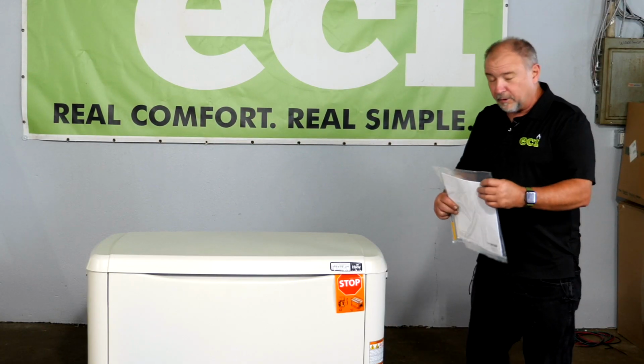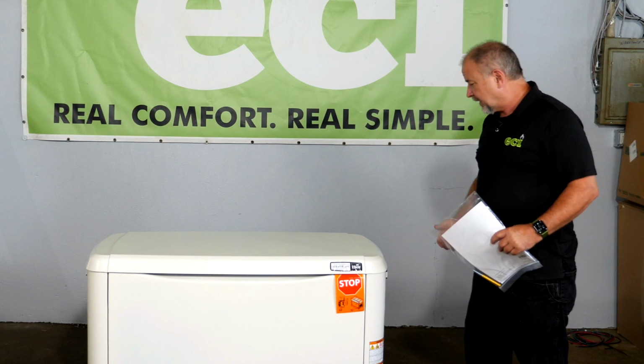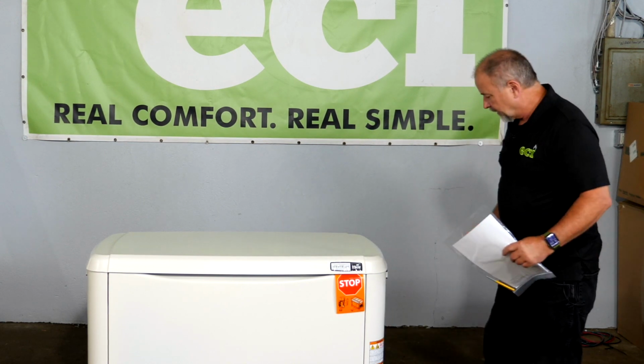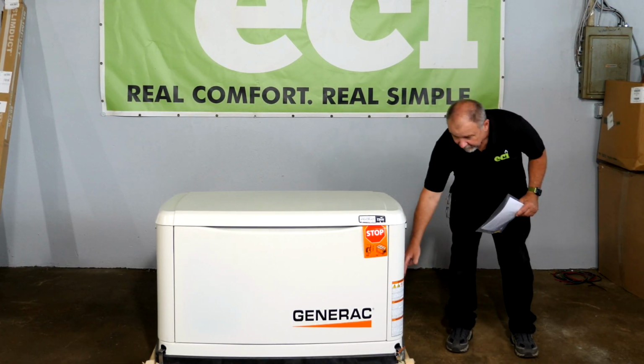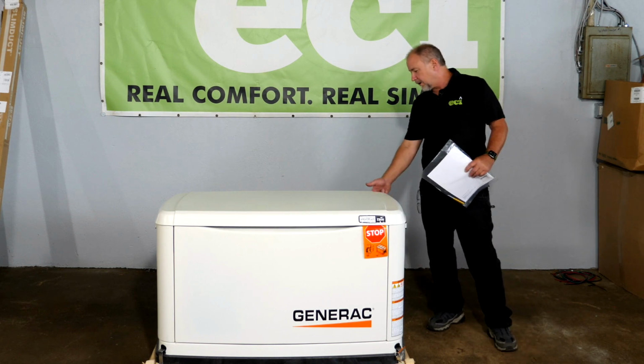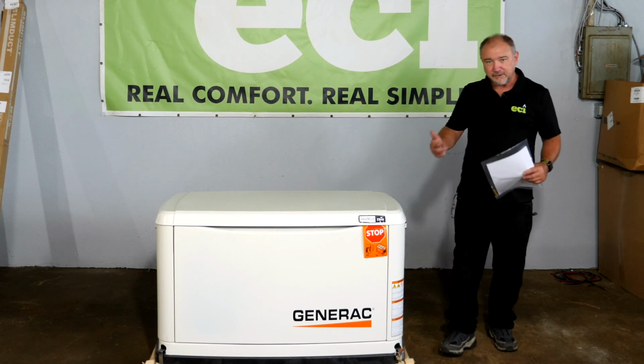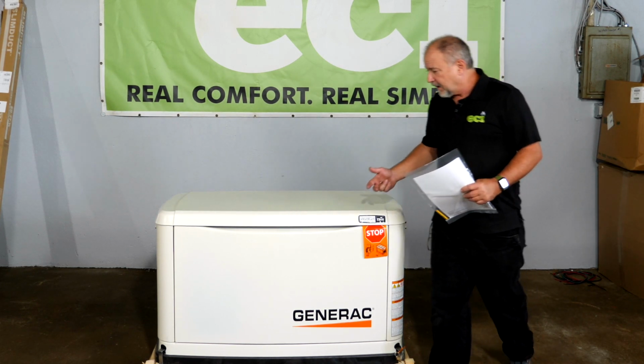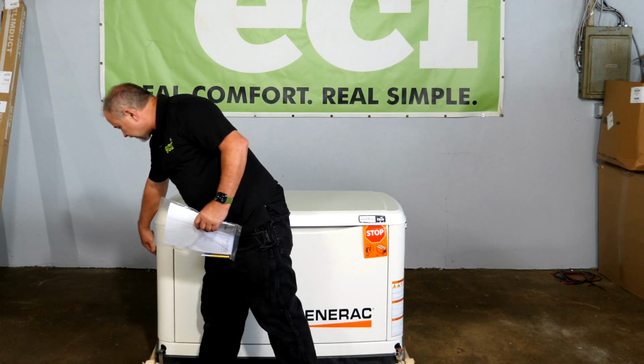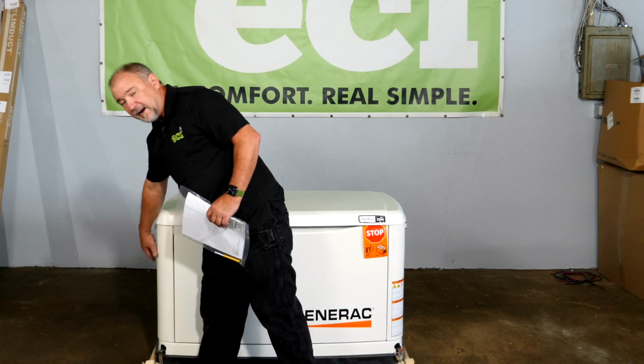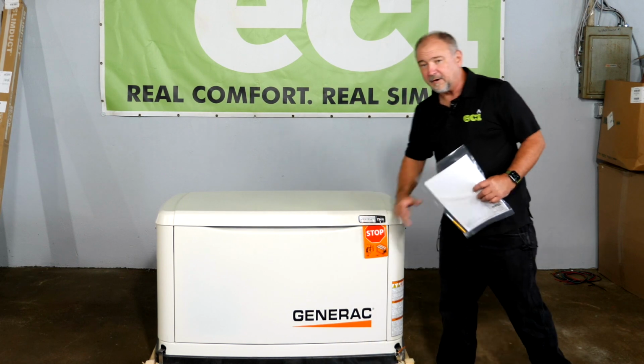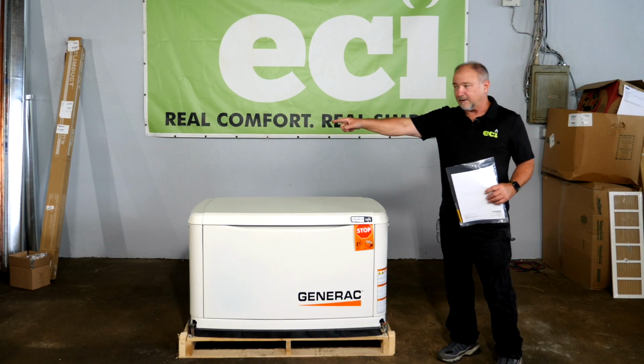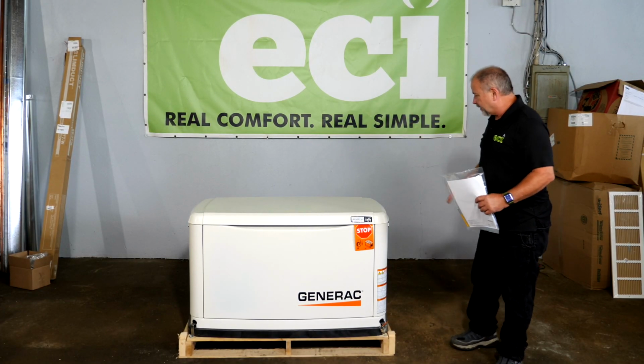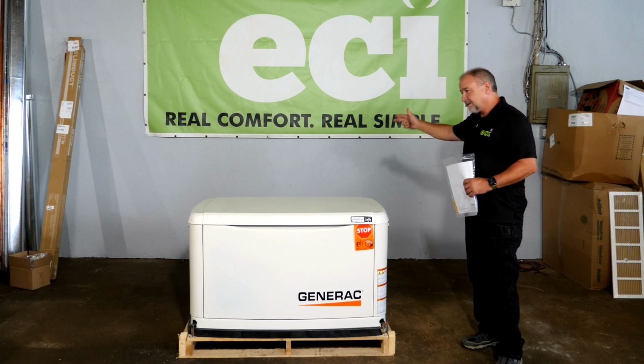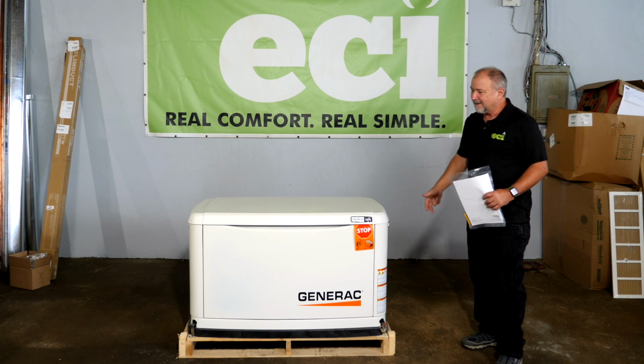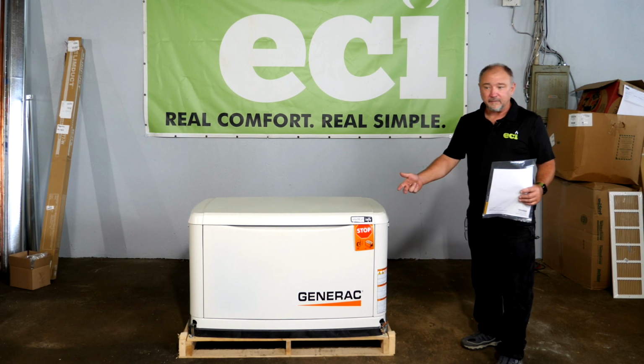The thing that's important for these generators is they need clearances. We have air that's taken in through here, and also the back, for fresh air, exhaust, and combustion. But the exhaust actually comes out this side of the generator, this being the front. We need 5-foot clearance on the exhaust side, 3 foot on this side, 1.5 feet in the back, 2 foot in the front so we can service it.